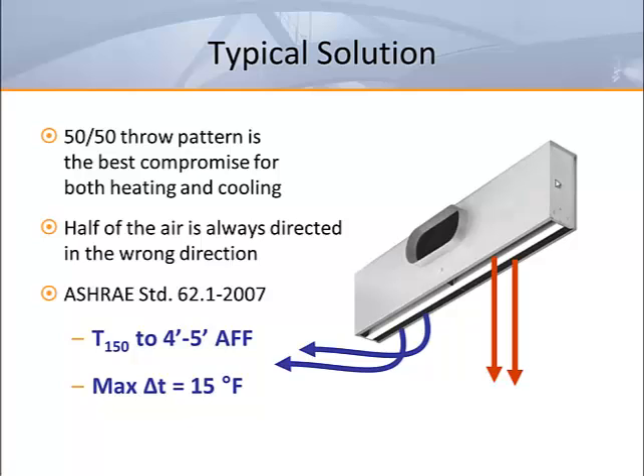For cooling and heating a perimeter space with a linear slot diffuser set for 50% of the air across the ceiling for cooling and 50% down the glass for heating, ASHRAE 62.1 says that the throw to 150 feet per minute must reach the 4.5 foot level above the floor. This helps to ensure that the ASHRAE Standard 55 requirement for maximum temperature gradient from ankle level to neck level will be less than 5.4 degrees. To maintain an EZ value of 1.0, the maximum temperature difference from supply to room must be 15 degrees. If higher, the EZ is 0.8, which means supplying an additional 25% ventilation air during the heating season.